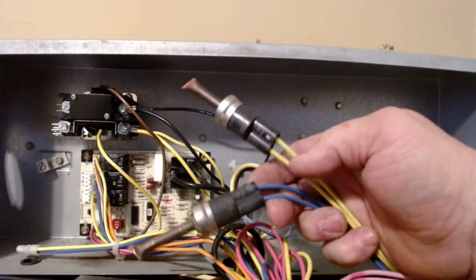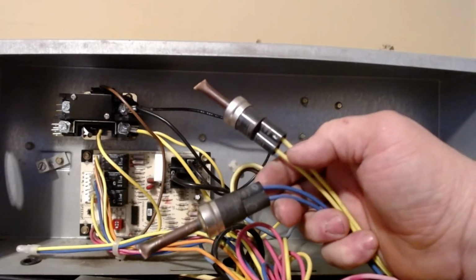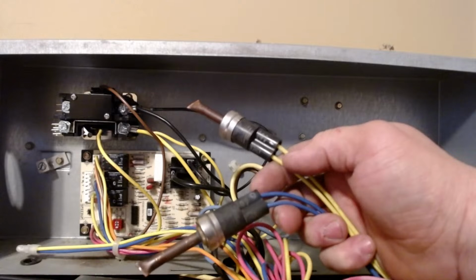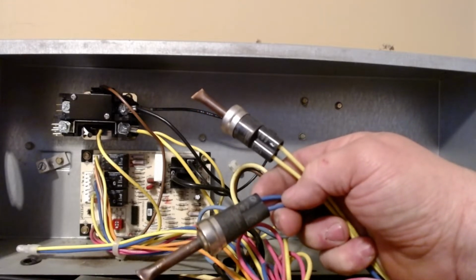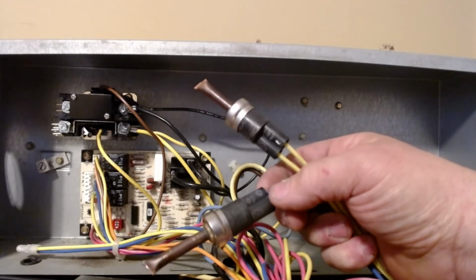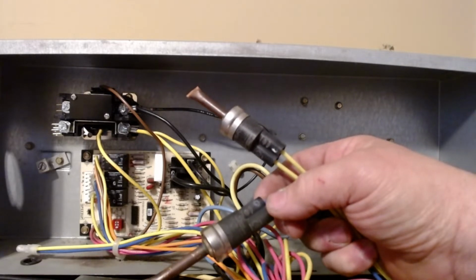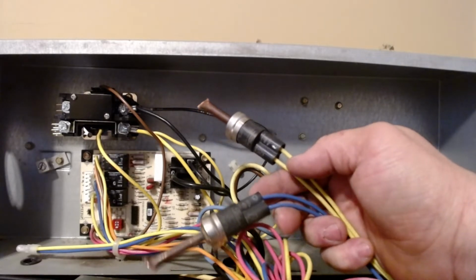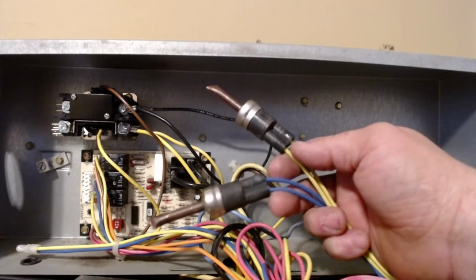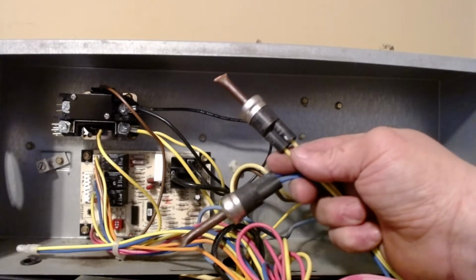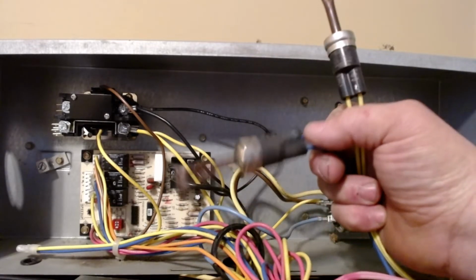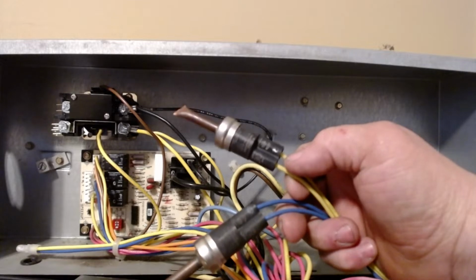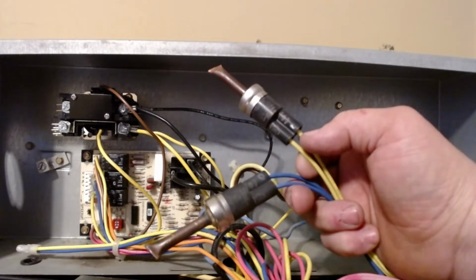So the difference between these two: out of the box, your low pressure will be open and your high pressure will be closed, because there's no pressure on the switch to force the switch to open up. Always go off the schematic to tell you which one is which, where they connect. Usually 9 times out of 10, your high pressure is on your discharge, your low pressure is on your suction. 9 times out of 10.